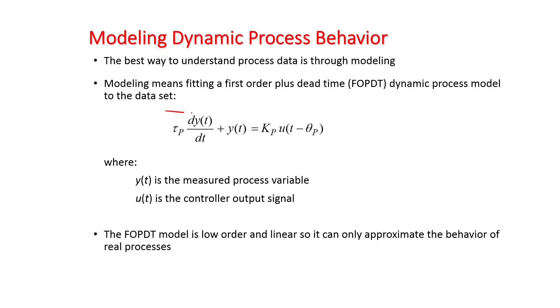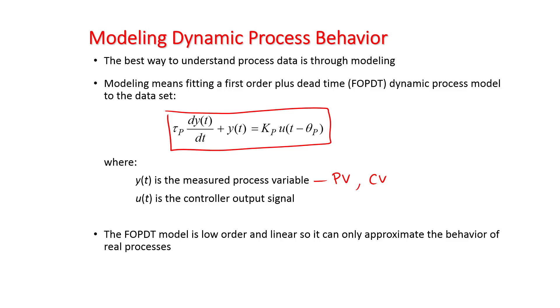For an introduction, we're going to use a very simple model: a first order plus dead time dynamic process model. The y variable — also called the PV, or controlled variable (CV) in model predictive control — is the output. The U is the input, also called the controller output, or in model predictive control, the manipulated variable. The first order plus dead time model is a low-order, linear representation, so it won't work well for very nonlinear systems, but it can approximate behavior in a particular operating region.